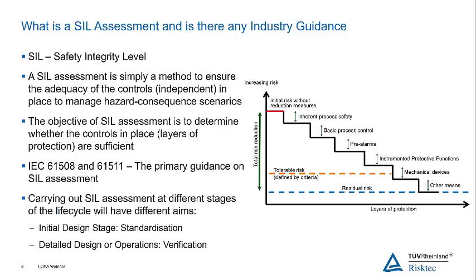manage these scenarios — these hazard consequence scenarios — to a level which we may consider to be tolerable or ALARP. The primary objective of the assessment is to analyse these controls, considering them as layers of protection, which you'll again see reflected in the name of LOPA, which is a layer of protection analysis study.